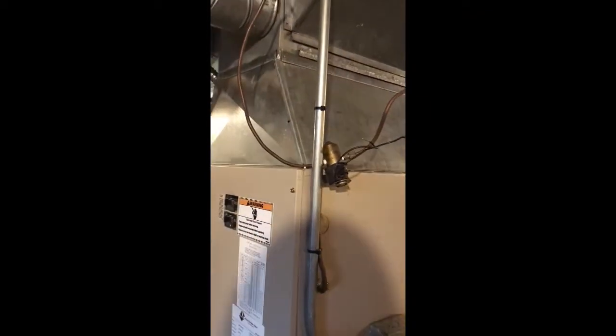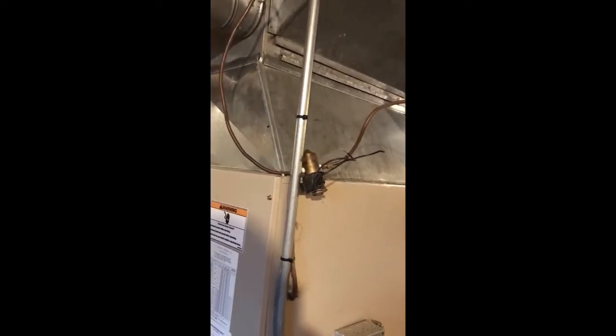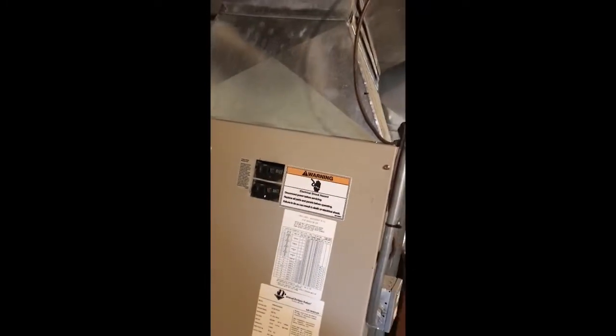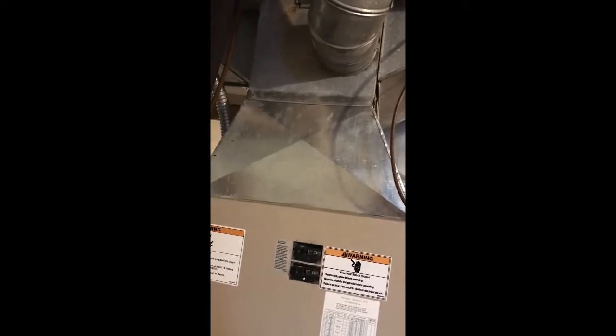Problem with these electric furnaces is they have very little room for a heat exchanger. If you open up the furnace, the hole for the blower is only about 15 by 12, going up into this plenum. The plenum at the top part is about 12 inches by 24, and I was able to find a heat exchanger that size.